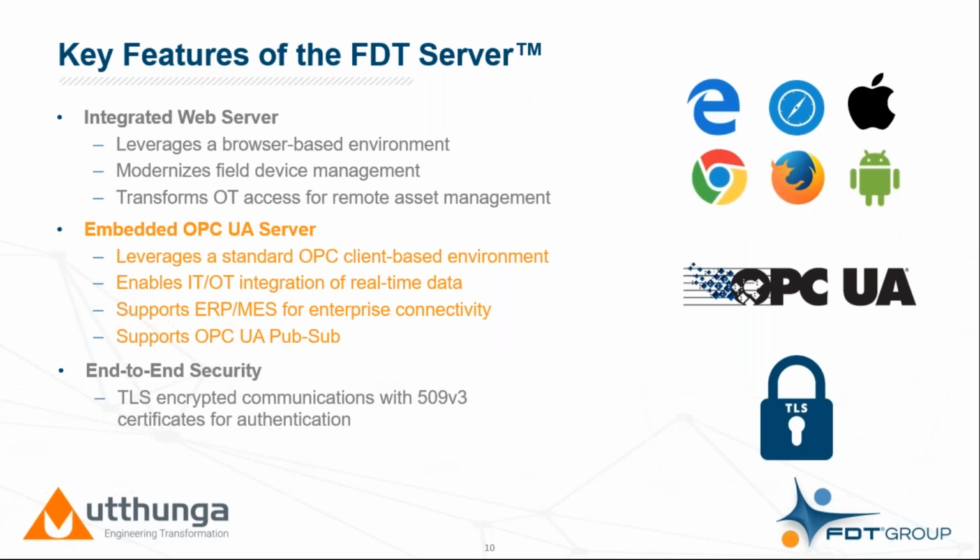So we've used industry standards for security that are well accepted both in the IT and OT organizations. So we use TLS as the standard, and we use X.509 v3 certificates for authentication. And we've taken security to the point where we can not only authenticate the user, but if you choose to, for your facility, you can also authenticate devices that a user may use to access the system. And of course, we maintain our traditional role-based access control so that you're able to categorize employees according to the role, and their security privileges follow that.